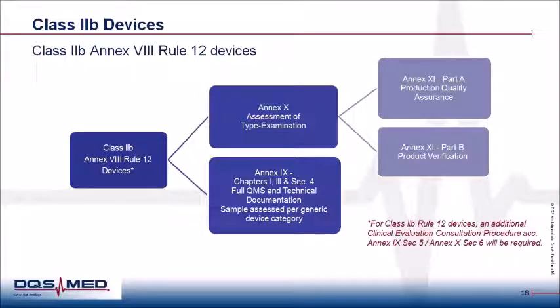As mentioned, Rule 12 is a new rule introduced by the MDR, and here, in addition, an expert panel involvement will be required to review these products. Here, the expert panel has to judge whether the clinical evaluation report is sufficient to provide confidence in safety and performance of the device, and whether an additional scientific assessment report is required. So in addition to the conformity assessment based on the annexes, there will be an additional scrutiny procedure, or the so-called clinical evaluation consultation procedure.